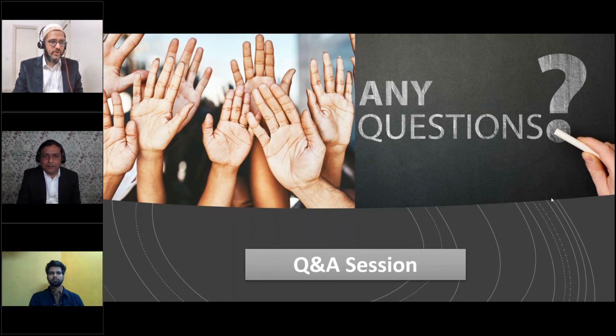Yeah. So Eric, there are different types of testing. One is design verification testing, which is the formal testing of your product, whatever product you have made. So what you formally test is design verification testing, and that comes in phase 4, the design verification stage. In the design verification stage, you will actually test your product. But the other testing can be design freeze testing. Some organizations, before even exiting the design development phase, want to make sure that whatever they have designed is meeting the requirement or not.